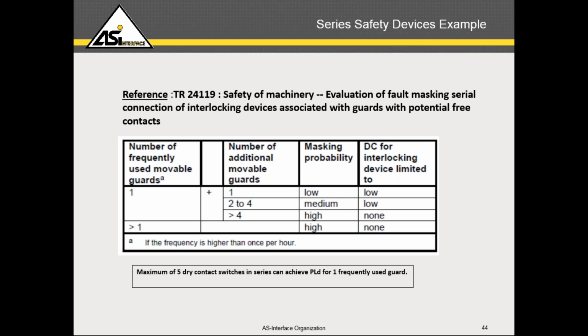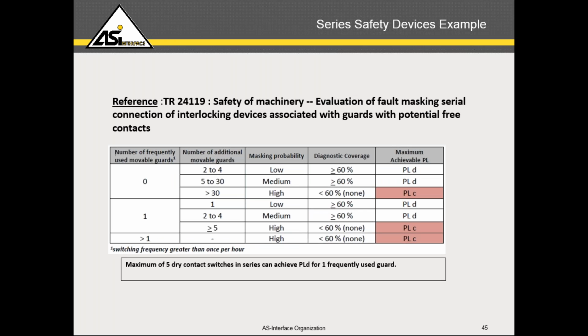In the technical report, it gives us even further detail: when we have more than 4 switches series connected, and one of the switches is frequently used, you may not actually get Performance Level D, Category 3. When we look at the actual table from the standard, it shows that from 5 switches series connected, with one switch being used frequently, more than once per hour, you may have a Performance Level C, Category 2 or Category 1, based on the application.